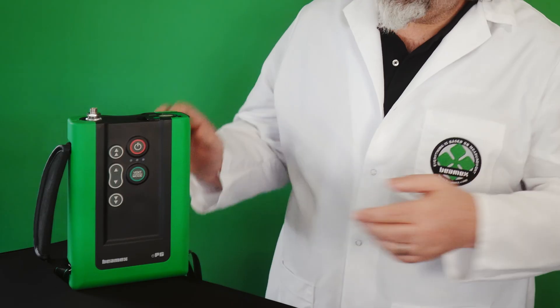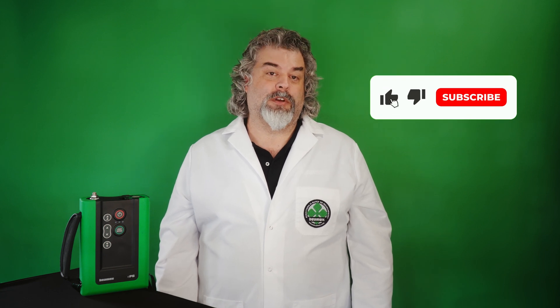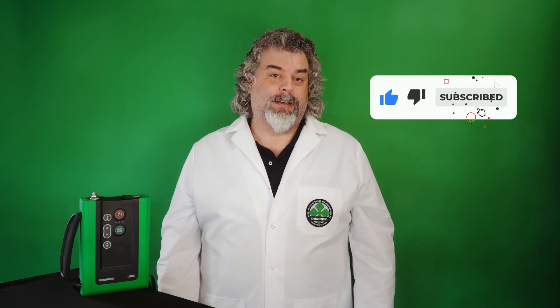The communication between the calibrator and the EPG is optional, so you don't have to use the automatic feature. You could just use the manual buttons on the front and achieve the same thing. But if I can do automatic mode, I'm doing it. To learn more on the Beamex EPG and to see it in action, visit the Beamex website or watch our other videos on our YouTube channel. Upgrade your calibration game. Thanks for watching.